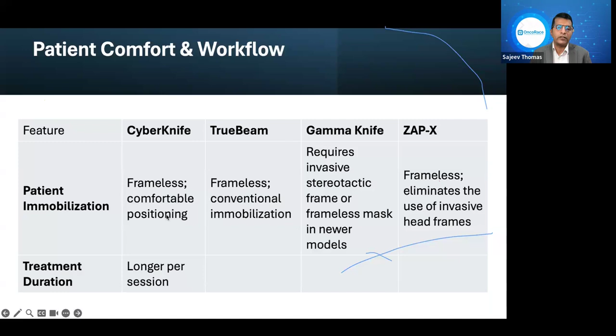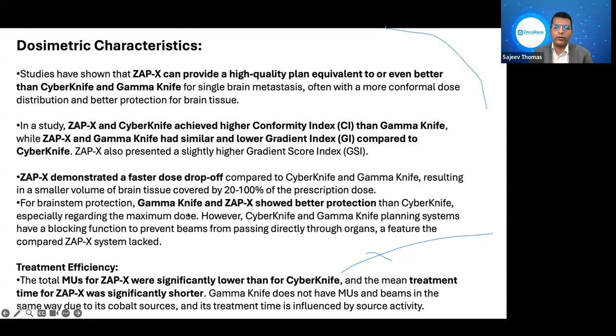And if you look at the technologies, the methodologies, Gamma Knife uses 192 fixed cobalt 60 sources for isocentric non-coplanar irradiation. CyberKnife uses a lightweight, high-energy LINAC with a robotic delivery system. ZAP-X uses a 3 MV S-band linear accelerator with a dose rate of 150 MU per minute and a mean energy of 1.15 MeV. And dosimetry characteristics, the performance: ZAP-X offers comparable or superior dosimetry quality to CyberKnife and Gamma Knife for single brain metastasis. And the dose distribution of ZAP-X demonstrates faster dose drop-off compared to CyberKnife and Gamma Knife, resulting in a smaller volume of brain tissue receiving significant dose. And treatment efficiency exhibits significantly lower monitor units for ZAP-X and shorter treatment times compared to CyberKnife and Gamma Knife.